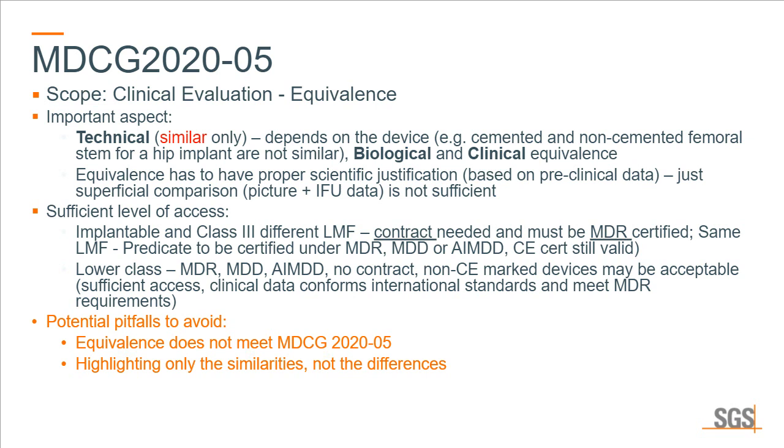For lower class devices, so this was for implantable and class 3s, for lower class devices, it can be certified to the MDR, MDD, or AIMDD. There is no formal contract required. The devices can even be non-CE marked so long as the legal manufacturer has sufficient access to the documentation and that the clinical data conforms to the international standards and meet the MDR requirements. There are some potential pitfalls to avoid. Yeah, basically, I think I already mentioned both of these points.